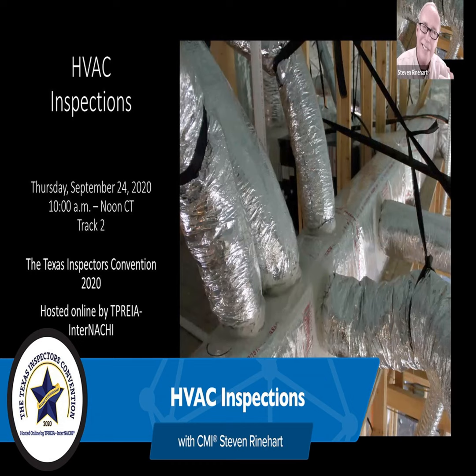Okay, we crank the burner up. Got to take the cover off really to do this. If it's a condensing furnace, you might be out of luck. You might be able to see it in the sight glass, kind of like looking in the sight glass of the new water heaters. You can't get a good view like we can in the old 50% water heaters or 80% furnaces. I like to look at the burner. I'll watch it start. I may stand back a little. Look at the flame, and what they want you to see is, does it have a good flame? Does it have a good blue flame?